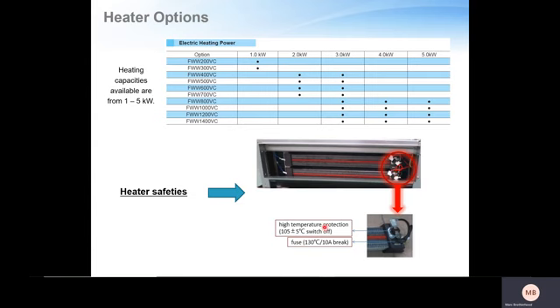If the bimetal switch fails, we have a fusible link that will open at 130 degrees. It's a little fuse in series with the supply, or if it pulls more than 10 amps, which are pretty much related. At about 130 degrees, the 10 amp wire will go open circuit, cutting the supply to the safeties. Further to that, once the fan coil is turned off on the thermostat, the fan will continue to run on for a further 60 seconds after the electric power down. That is just to dissipate any heat, and also so you don't get that burning smell in the air.